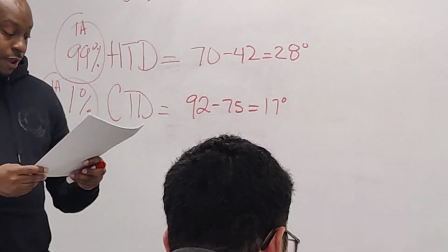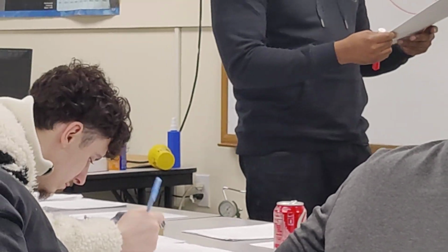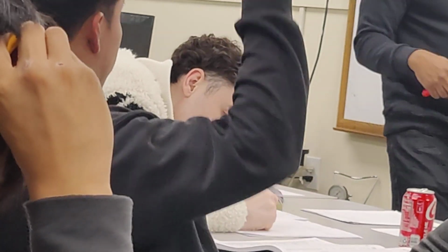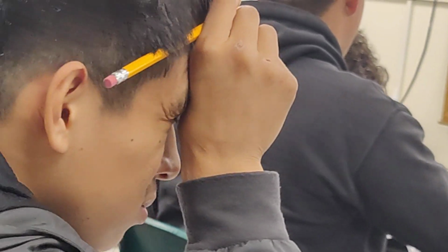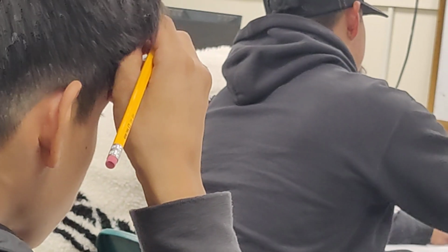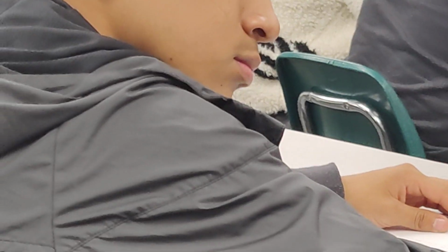Now we're going down on the first page to where it says heat transfer multiplier (HTM). This is the U value times the temperature difference. You might want to highlight it, underline it. You're going to need this formula. Remember, the U value is found on, can anybody tell me what chart? 2A or 3A.